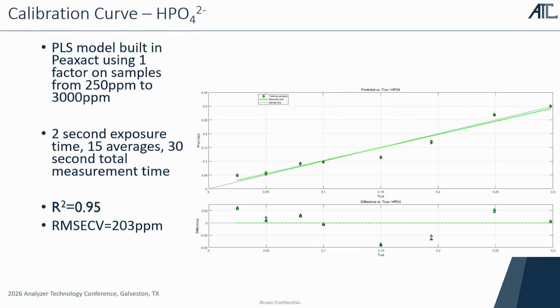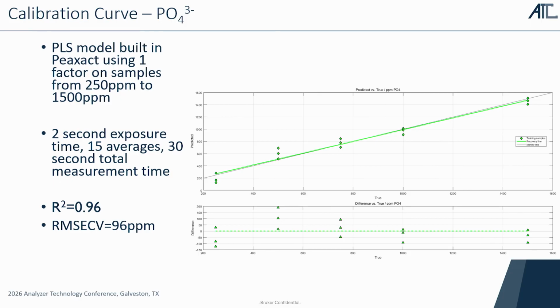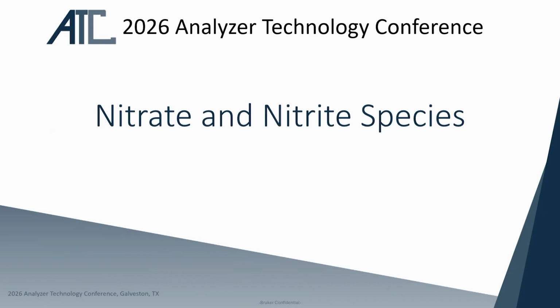So 2-second exposures, you know, again, R squared of 0.95, error of cross validation of 203, right? So this is from 250 ppm to 3,000. Also important to note is just that these ppm levels were just what we had at the time. This is not some set in stone level of accuracy that these things can go to. They can actually go lower than this.